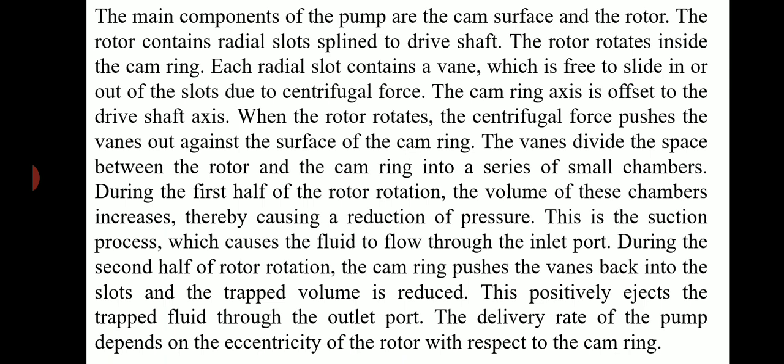When the rotor rotates, the centrifugal force pushes the vanes out against the surface of the cam ring. The vanes divide the space between the rotor and the cam ring into a series of small chambers. During the first half of the rotor rotation, the volume of these chambers increases, thereby causing a reduction of pressure. This is the suction process which causes the fluid to flow through the inlet port.